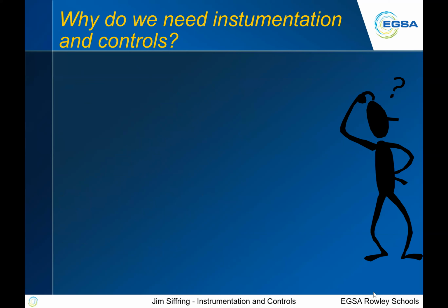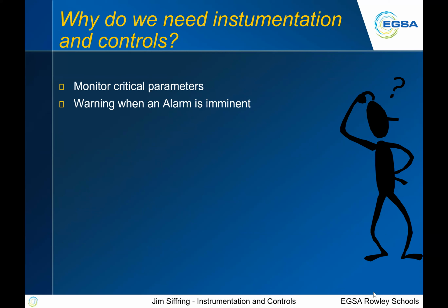So, excuse me. Why do we need instrumentation and controls? So what are we going to do? We're going to monitor the critical parameters of this genset. We're going to hopefully send an alarm or a warning when an alarm is imminent. There's two basic stages to controls. You want to have a warning that says, hey, something's about to happen, and an alarm that says something did happen. So we'd like to have that warning first and tell us before the alarm happens. But we do want it to alarm if a parameter is met or exceeded.